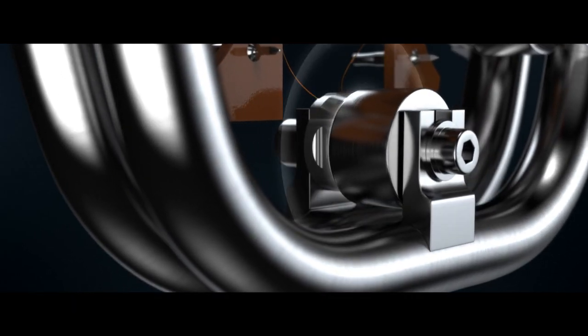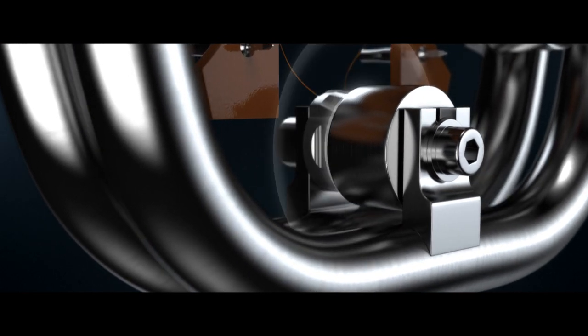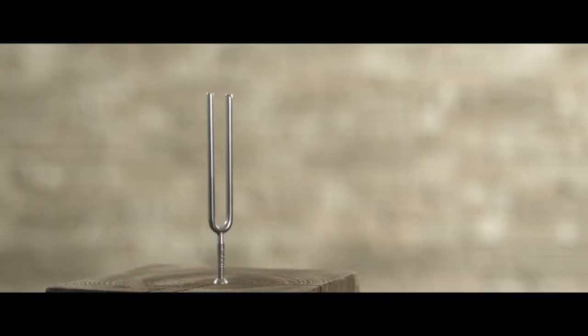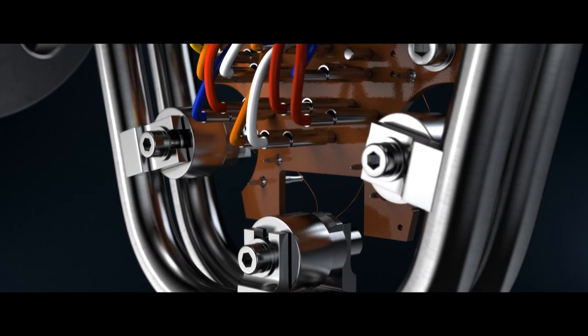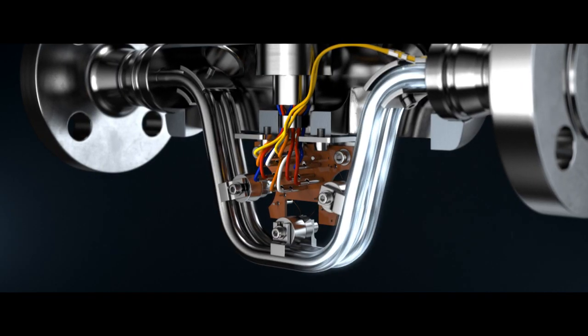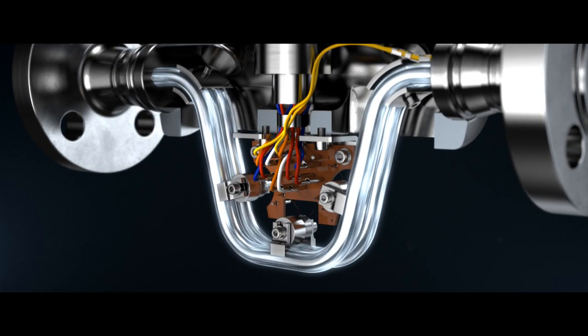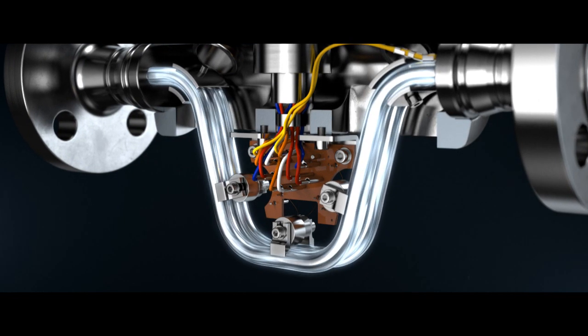The tubes oscillate with a resonance frequency, similarly to a tuning fork. The oscillation is measured precisely by two pickups at the inlet and outlet sections. If liquids or gases now flow through the tubes, a phase shift occurs.